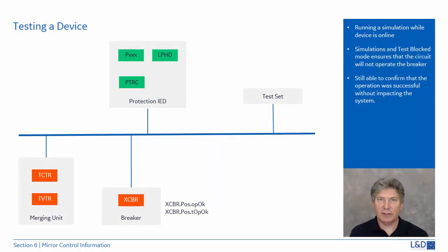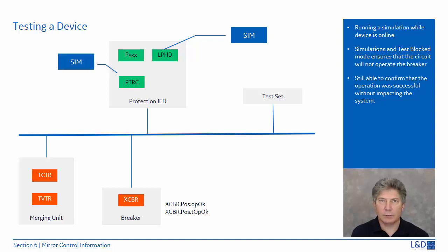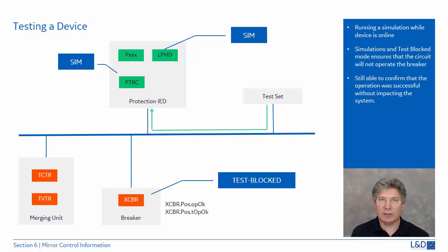Let's review how it's possible to test a device that is connected to the system. In our example, we want to test the performance of a main protection that receives sampled values from a merging unit and trips the breaker through a breaker IED over a process bus. In the logical node LPHD of the main protection relay, the data object SIM shall be set to true. The logical device for the protection function shall be set to mode test. And a logical node XCBR for the circuit breaker shall be set to the mode test blocked. A test set will send a sampled value with the same identifications as the ones normally received by the protection IED, but with the simulation flag set to true.